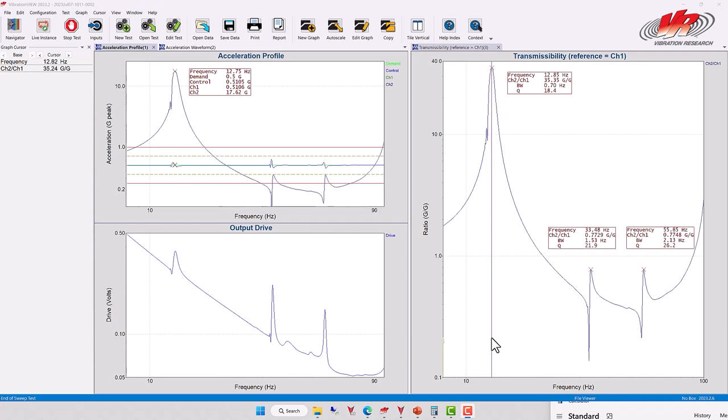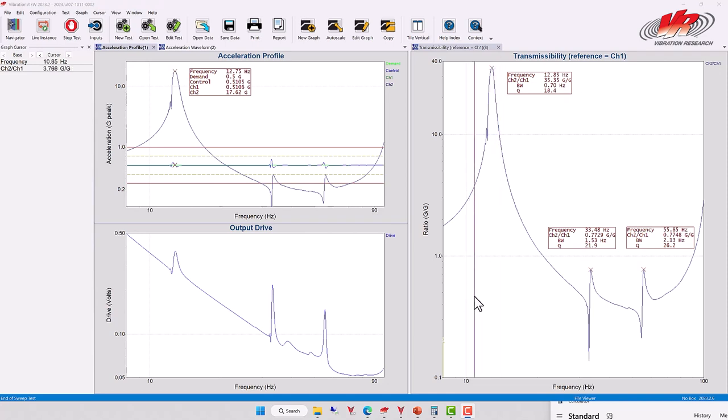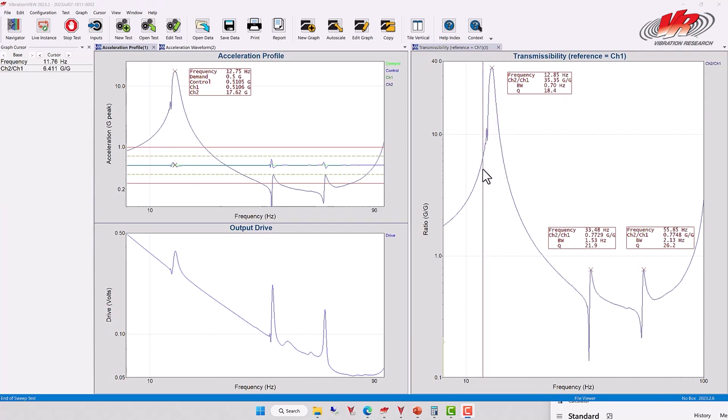In summary, in this video we have explained that a resonance has a peak value or an amplitude. That value is very important to a test engineer because it describes how much acceleration the device under test is experiencing at that particular frequency. The resonance also might occur over a very narrow band of frequencies. In that case, it would have a high Q value or be described as a narrow bandwidth, or it might occur over a broader band of frequencies described as a low Q value or a broad bandwidth.